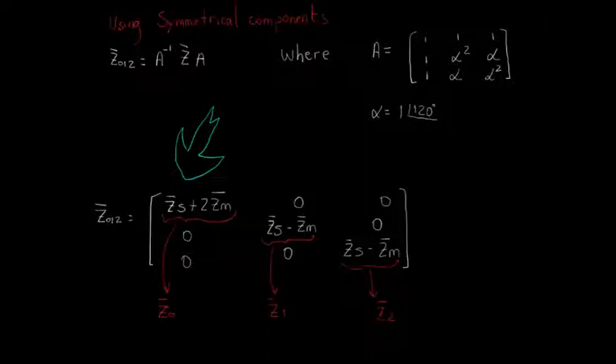These elements Z0, Z1 and Z2 can be directly used to describe part of the vSource element in OpenDSS as we will see later at the end of this video. We can also describe the impedances of the vSource element either with the pair line-to-ground short-circuit current and three-phase short-circuit current, or three-phase short-circuit power and single-phase short-circuit power. So now we will find expressions for these currents and powers.